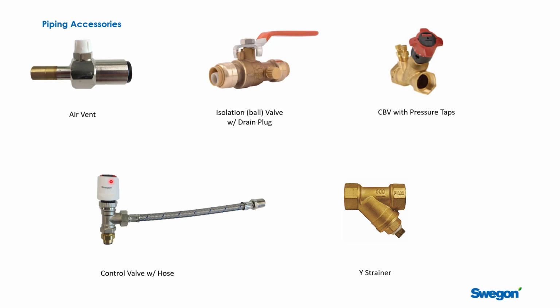As the heat warms up, the wax expands and it pushes the plunger down, opens the valve, and then when the space is satisfied, the 24 volts to the actuator, that circuit's broken, and the wax cools down, and over a few minutes that valve slowly closes. It slows the valve actuation down so that you're not opening in 10 seconds or 20 seconds, running for a few minutes, and then closing. You're taking 2 or 3 minutes to go through a cycle, and it just helps smooth out the condition. So a very popular thing to see done in Europe, a little less so in North America. And you see it all comes in an assembly.